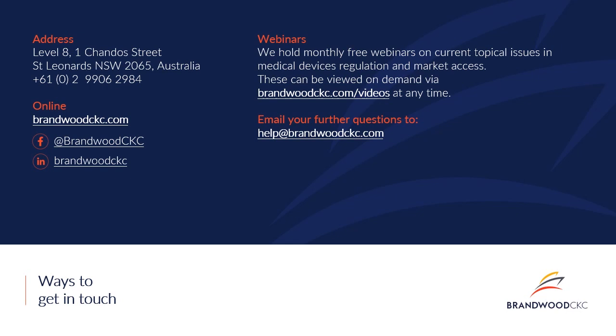I guess the key thing here is that it is an evolving document. So if there is new information coming in, then the clinical evidence report should be updated. If not, then at least annually. If you're able to justify that the clinical evidence report is able to be updated every 2 to 5 years, then you're able to do that.